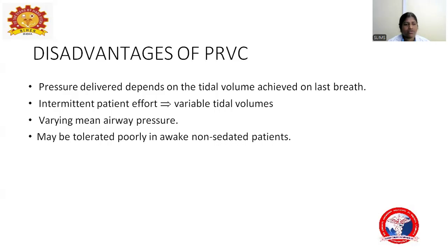If the patient is not taking breaths continuously, then the ventilator will provide variable tidal volumes because the patient is having intermittent efforts and varying mean airway pressure. And this method may be poorly tolerated in awake non-sedated patients.